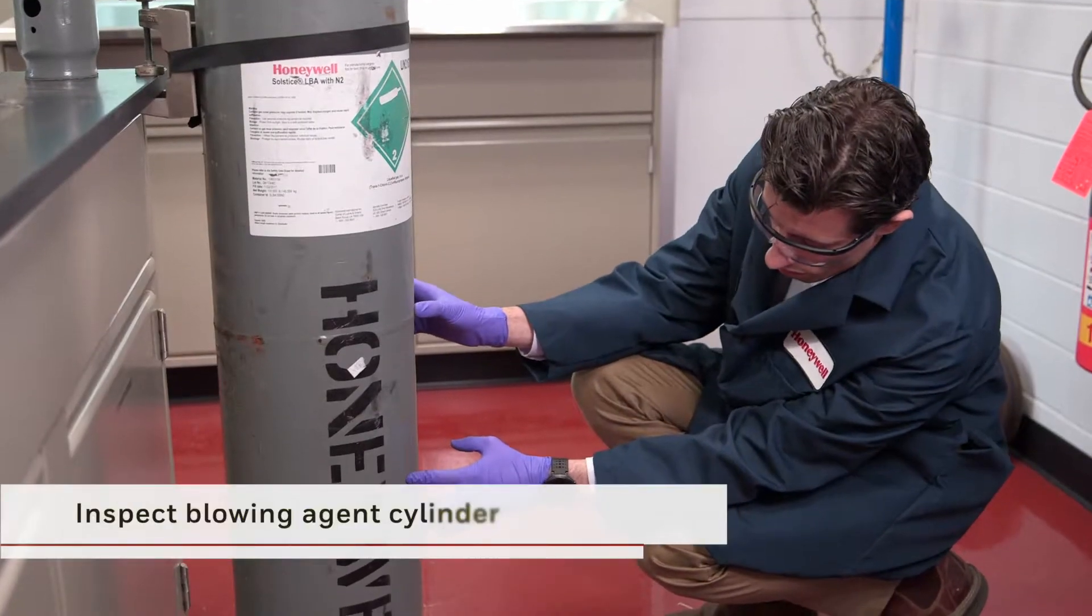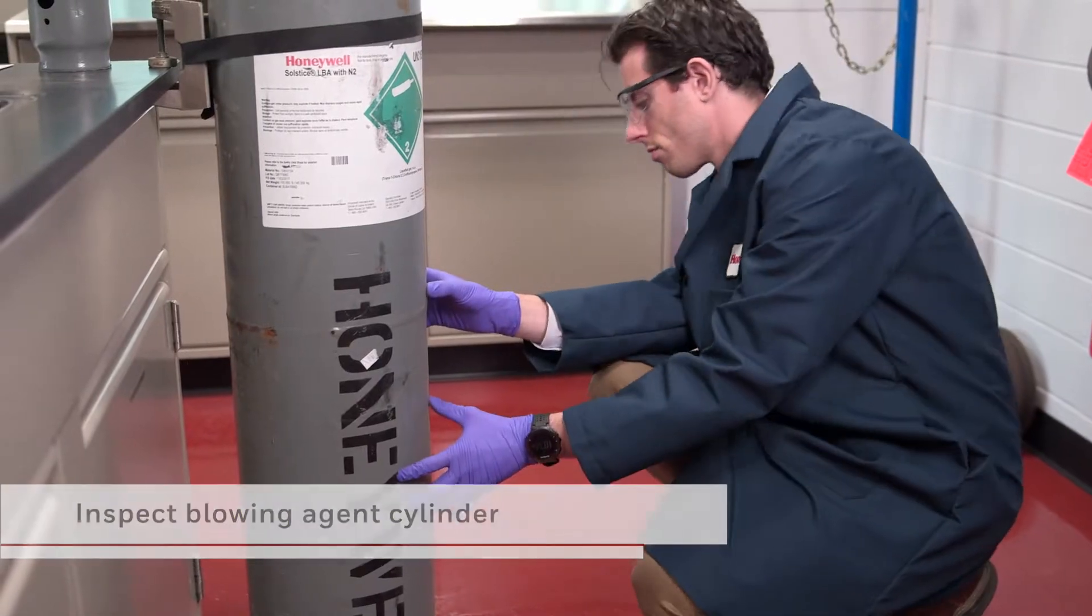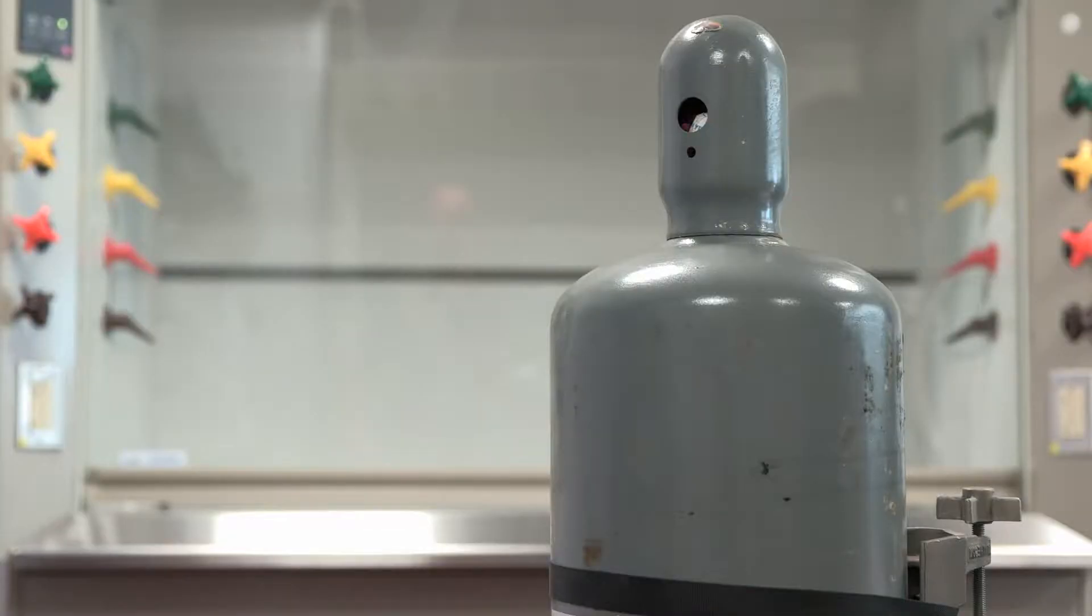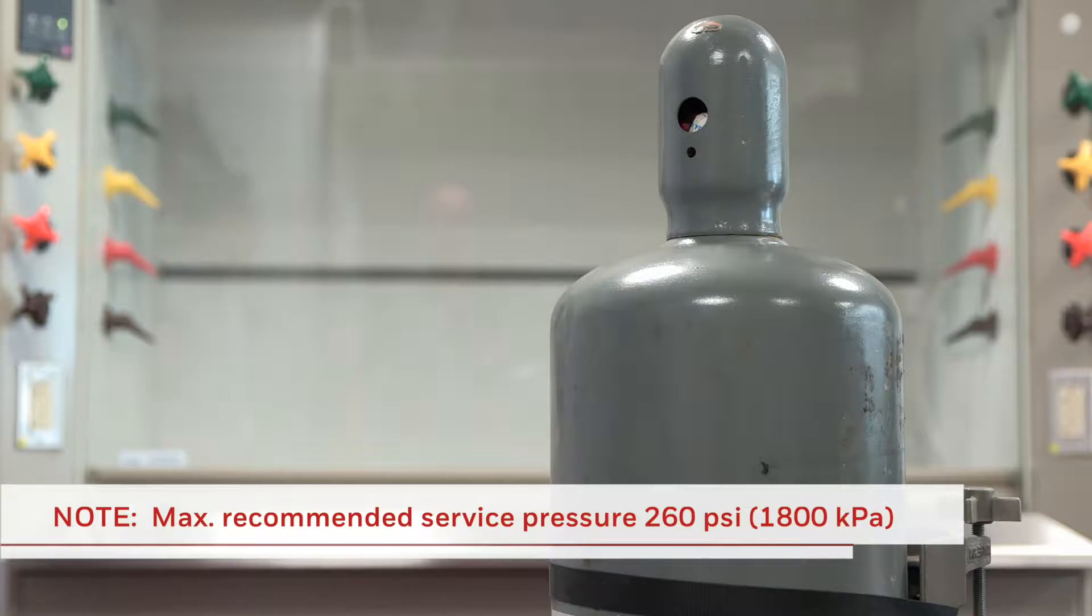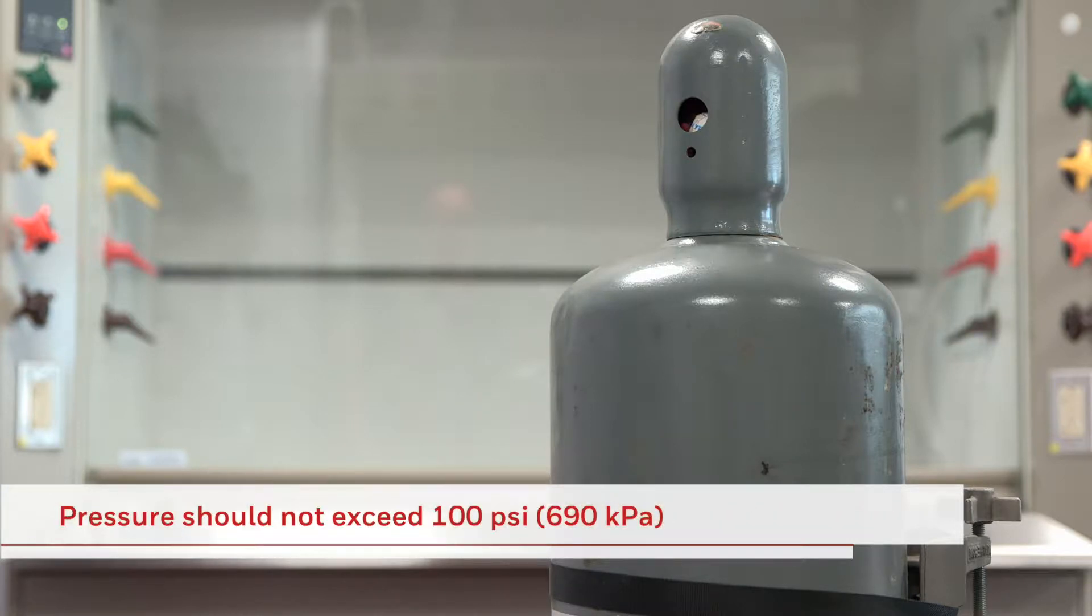First, inspect the blowing agent cylinder. These 100-pound cylinders are designed to be used vertically. The maximum recommended service pressure is 260 psi, or 1800 kPa, and there's no practical need for cylinder pressure to exceed 100 psi, or 690 kPa.